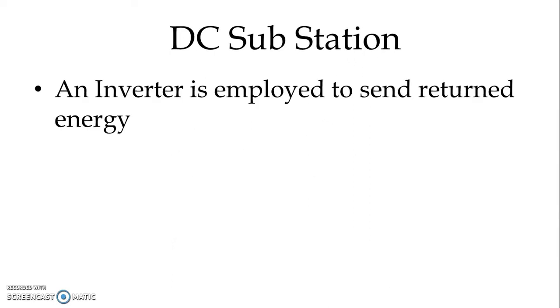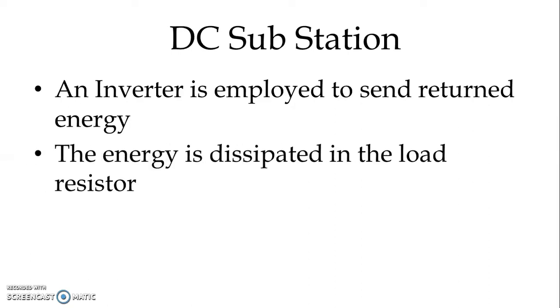The rectifiers we use are non-reversible type. When energy is generated during regenerative braking, this generated energy needs to be supplied back to the grid. So we install grid connected inverter to send back the return energy, or else the energy is dissipated in the load resistor.